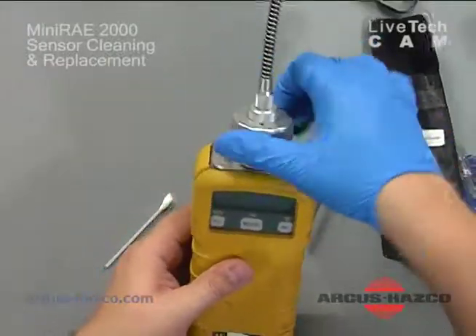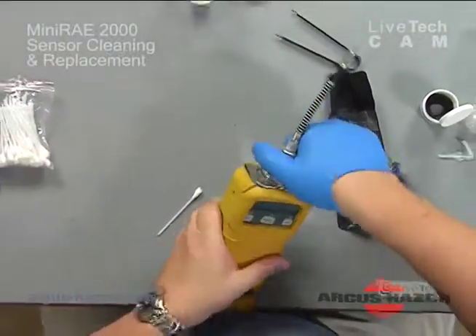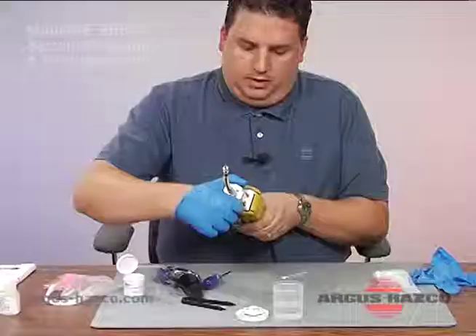You screw that probe on. You may have to screw it a little bit tight until you can't screw it anymore and everything is adjusted, and you've either cleaned and/or replaced your lamp or sensor on the MiniRAE 2000.